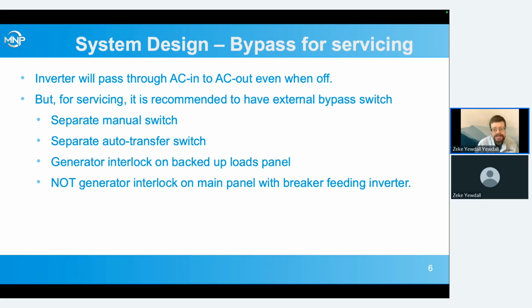Another way to do this is on your backed up loads panel, put a generator interlock where you've got a main breaker and then a back-fed side breaker. And one of those is fed by the inverter output, and one's fed by another feed off of the grid panel. And they've got a little mechanical interlock, so both of them can't be on at the same time. That way, if you're servicing the inverter, you can flip that interlock and still feed your backed up loads from the grid.